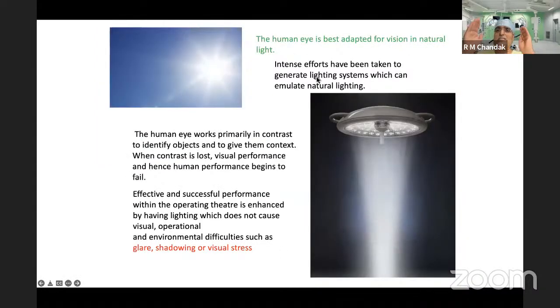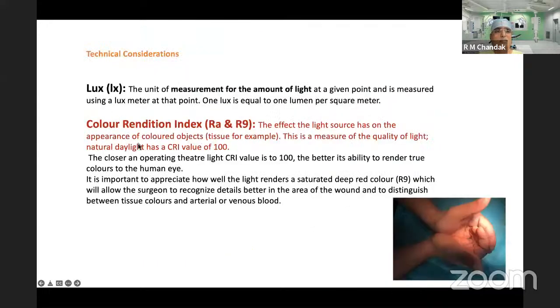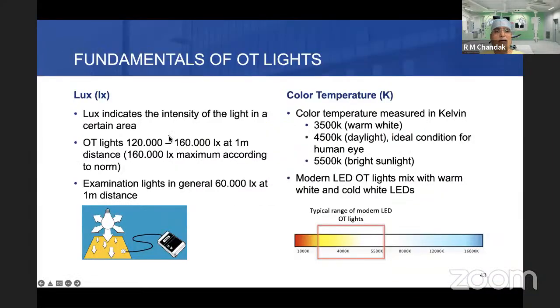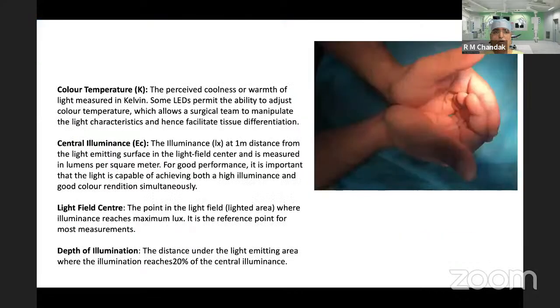Coming to OT lights, we had halogen and the modern day LED light. The human eye is best adapted for vision in normal light, and the modern day light should avoid glare, shadowing, or visual stress to us. The light is measured in terms of lux, and the lux intensity has to be between 1,20,000 to 1,60,000, which is the best, and choose a light accordingly. The color temperature, the central illuminance, the light field center, all these aspects we have to take into account when we choose a proper light.